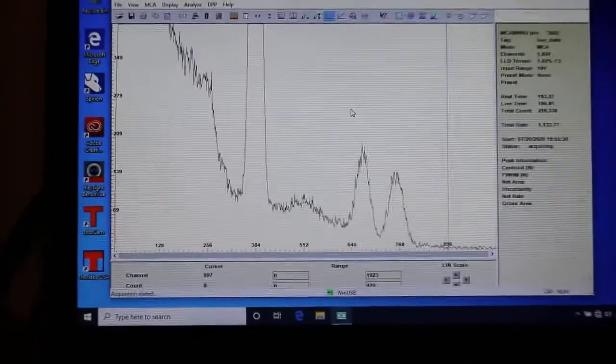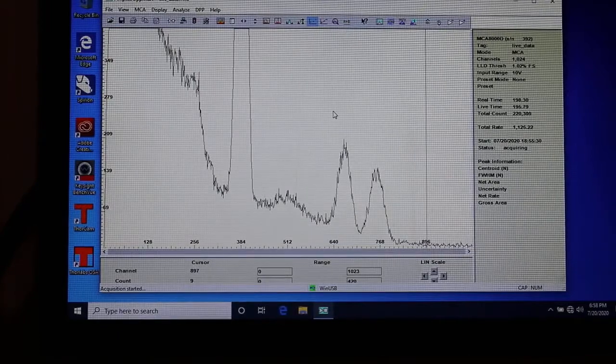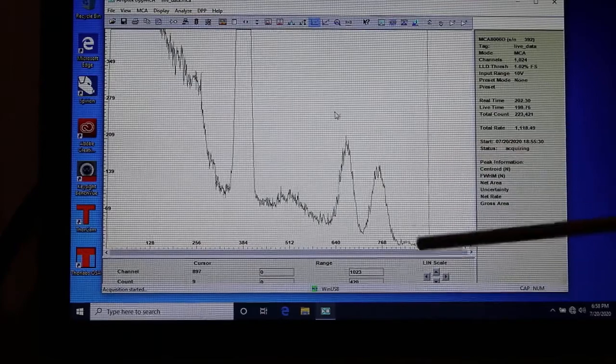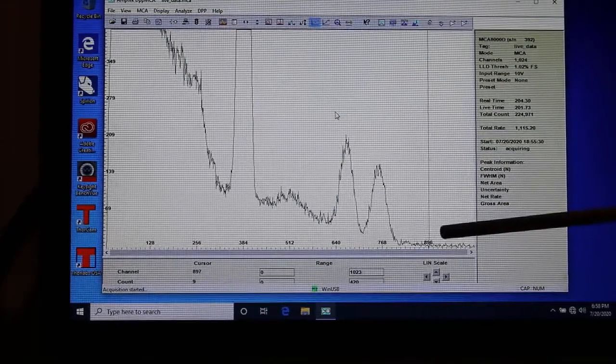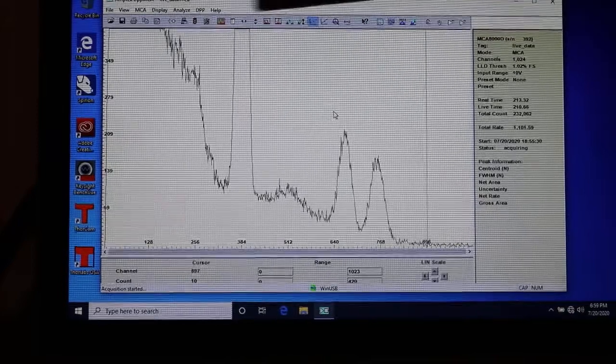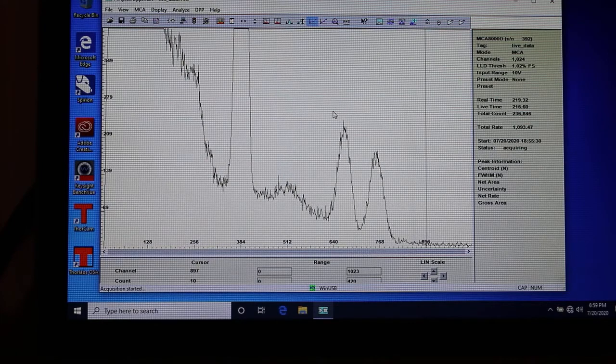We don't want to do that. Since we know cobalt is the highest gamma ray energy emitter, we're going to tweak the amplifier settings to put these photopeaks right here in this area of the screen. Everything else that we put on the detector, all the other sources like the barium and the sodium-22, is going to have its peaks fit in some of these lower energy channels. So we'll have a nice consistent channel set among all of our sources. Then we can get in and start talking about calibrating the x-axis.